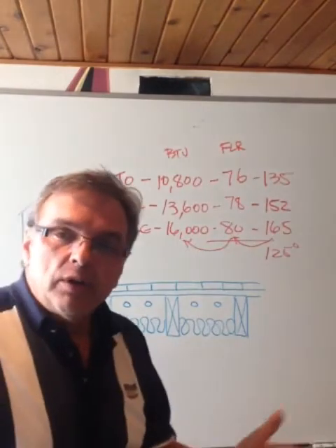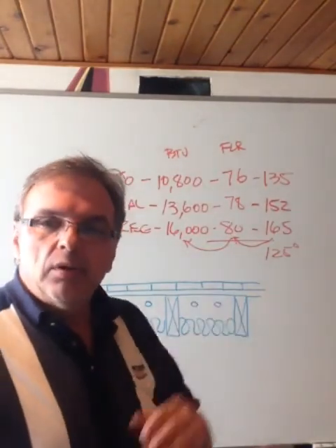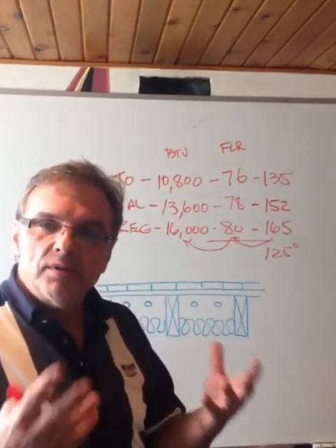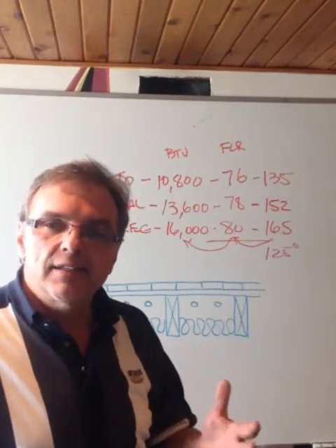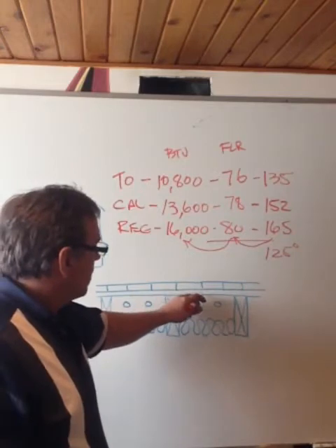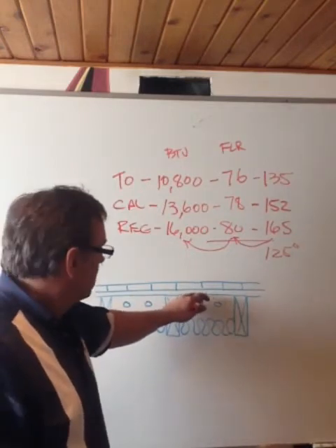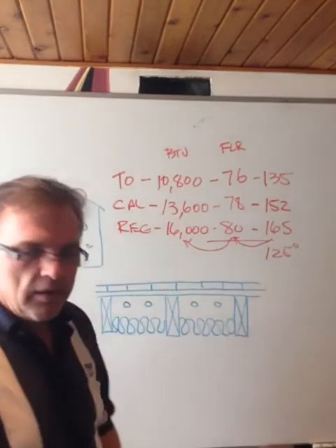Because think of it, floor covering, the more floor covering you put on top of the tube, the more resistance you're creating. It's just like adding insulation to the wall. So the thicker this floor is, the hotter this point needs to be to get the proper temperature here. Okay, so what can you do?